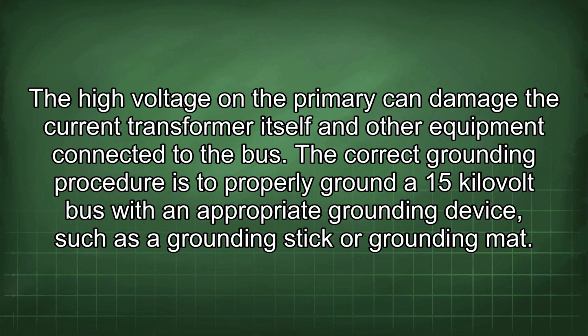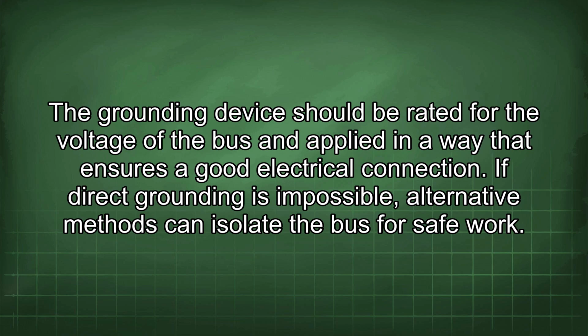the bus. The correct grounding procedure is to properly ground a 15 kilovolt bus with an appropriate grounding device such as a grounding stick or grounding mat. The grounding device should be rated for the voltage of the bus and applied in a way that ensures a good electrical connection. If direct grounding is impossible, alternative methods can isolate the bus for safe work.